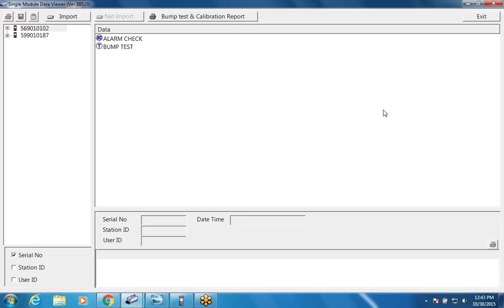I can't see why we would ever need that unless you weren't using a 4-gas mix—you get a bunch of different toxics. But you can only have 2 of those. Mike makes the best point, which is if you had 10 units ganged together and multiple combinations of sensors you wanted to calibrate at once, that's probably when you'd use it. Also, if you had a different LEL gas for the LEL sensor where you couldn't use a 4-gas mix, that might be handy. But there aren't a lot of places you'd use it, since we have 3 ports on the standard unit—it's available as an option for people with a big fleet and a bunch of different combinations. Maybe a rental house would use that if they've got a lot of instruments and they're swapping sensors in and out all the time.